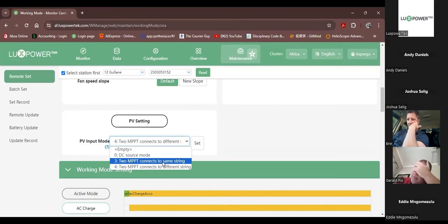So let's just say, for instance, you've got panels on the roof, 5 and 5, and your open circuit voltage is, I'm going to use a round number, 200 volts per string. And the short circuit current rating of the panels is 10 amps. If you parallel the two strings on the roof, it'll then become 200 volts, 20 amps. And you can then bring that down through a 6 millimeter cable or a cable that's rated for the current rating. You bring it down and then on your PV board, before it goes to the inverter, it'll come in.